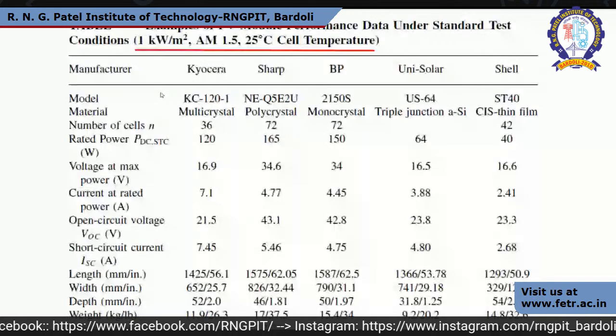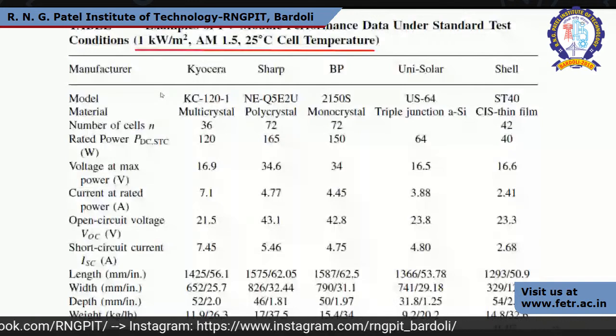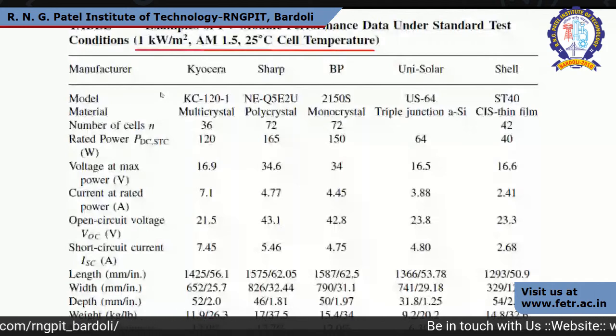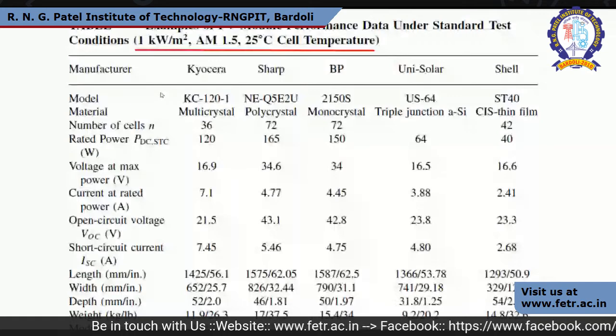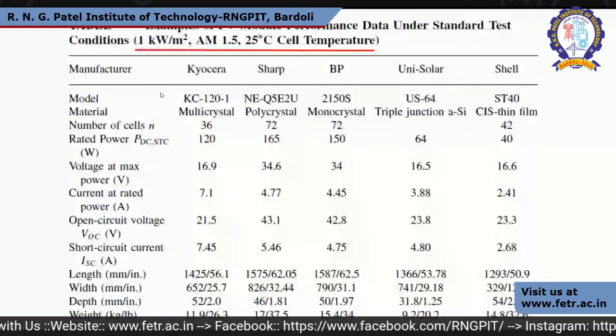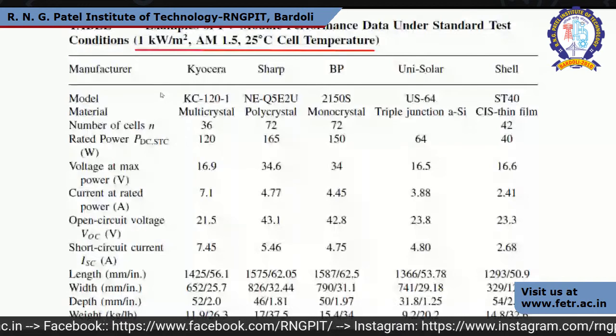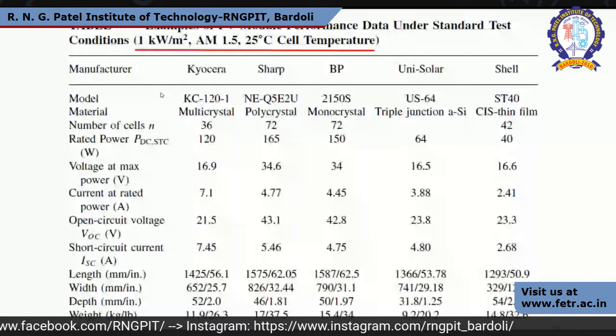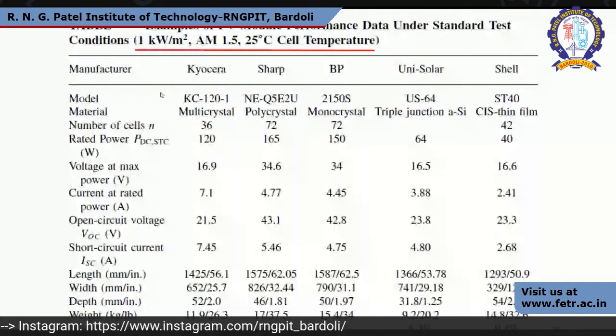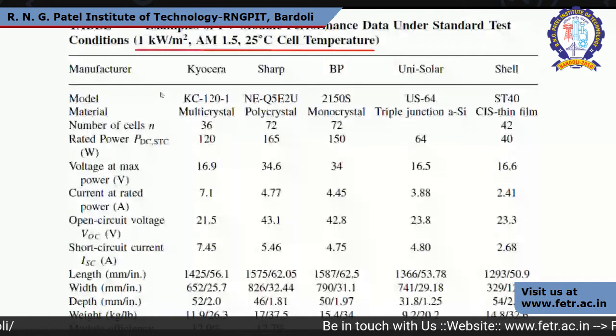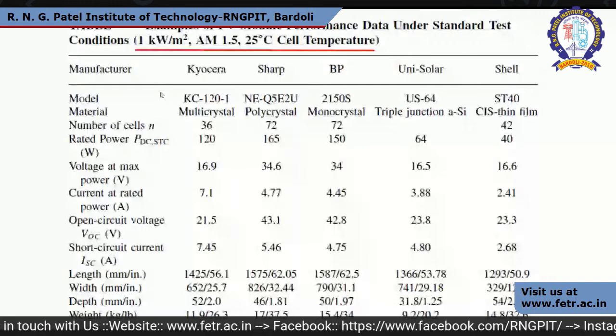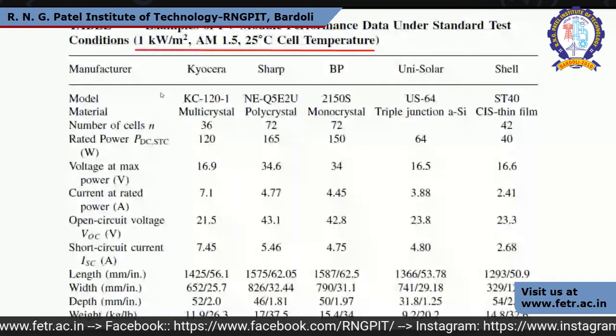Peak power or DC power at STC is 120. The voltage at Pmax is 16.9. Rated current is 7.1 ampere. Open circuit voltage is 21.5 volt. Similarly, short circuit current is 7.45 ampere. So if we are maintaining this condition and we are short circuiting this panel, we will be able to get the value of 7.45. And at last, with some mechanical dimensions, the module efficiency is 12.9%.